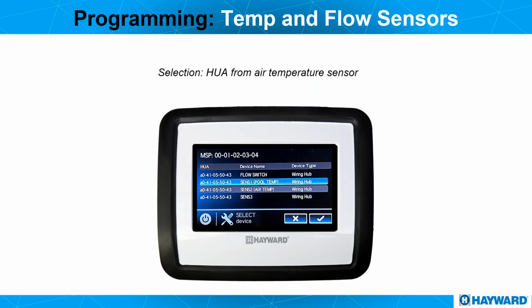Why do we need a water sensor in our system? The system needs to know what temperature the water is in order to turn on a heater. This is for safety, if it doesn't know the water temperature, it's not going to turn on a heater. It's also going to ask us for an air sensor. Yes, we'll choose sensor number two, air temp, and this is very important to have for those areas where we choose freeze protect.